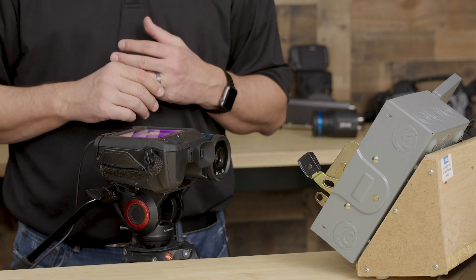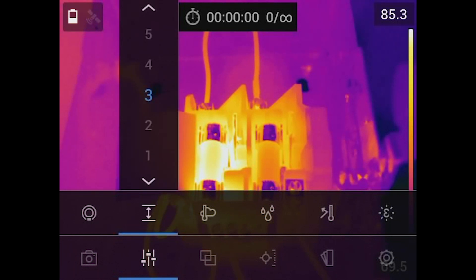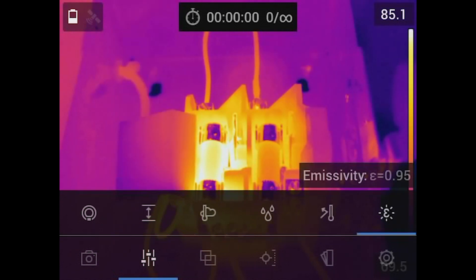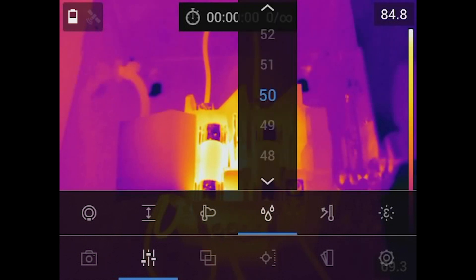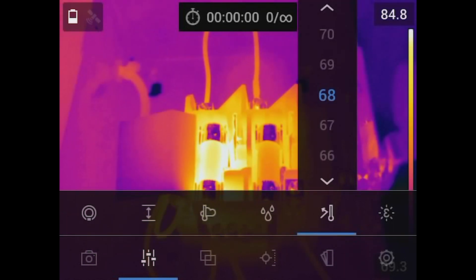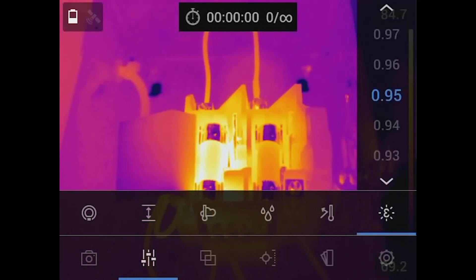Here we can go ahead and change the object distance. When set up for outdoor targets, we can set a distance from the camera to the object — in feet or meters. For indoor work, we really don't need to set that. Also in the menus, we can change the atmospheric temperature, and for long-distance outdoor work, you'll want to use settings for humidity and reflected temperature, and of course our setting for emissivity. Different targets emit differently in the infrared spectrum, so here we can set our emissivity value.